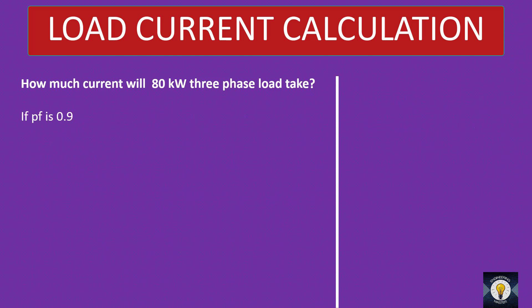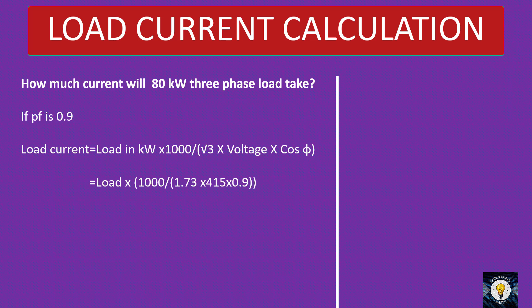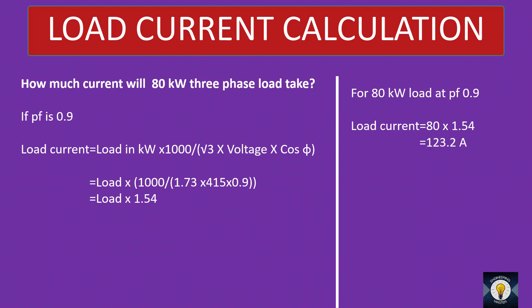If your power factor is 0.9, what will be the multiplier? The equation is load current equals load in kW into 1000 divided by root 3 into voltage into cos φ. Substituting: load into 1000 divided by 1.73 into 415 into 0.9 — the value will be load into 1.54. So if your power factor is 0.9 and line voltage is 415 V, remember the multiplier 1.54. Just multiply the load by 1.54 to get the load current.